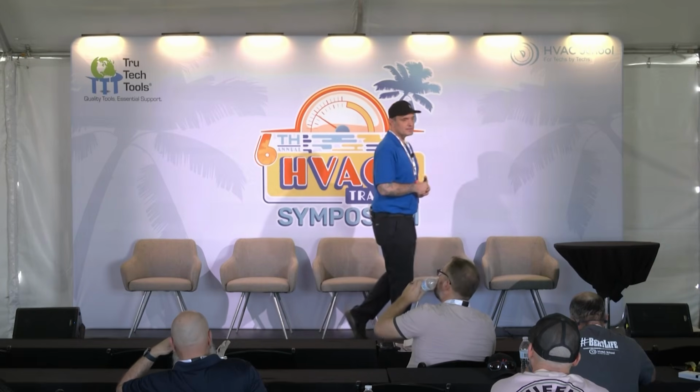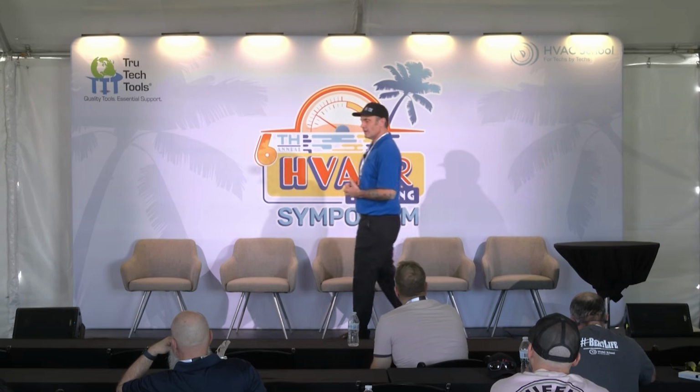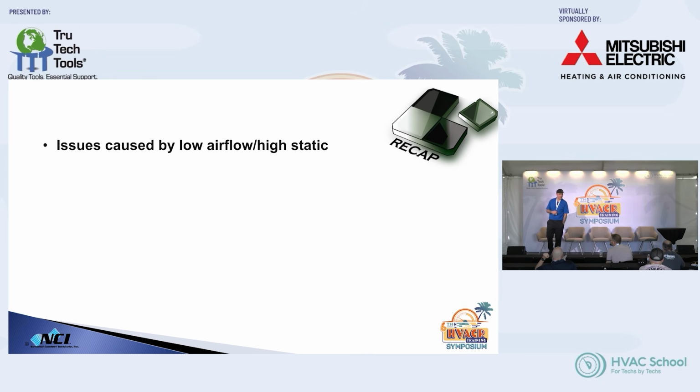When we pay attention to sizing, and I know you guys use Conduit Tech, QuickModels, there are all these different companies that we could use to try to figure out what our load is. Paying attention to the load is going to increase comfort. You're going to reduce your duct pressure, you're going to reduce duct leakage, and you're going to swing that pendulum much farther in the correct direction by installing a smaller system. So our recap: issues caused by low airflow and high static.